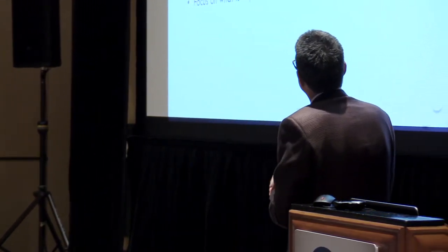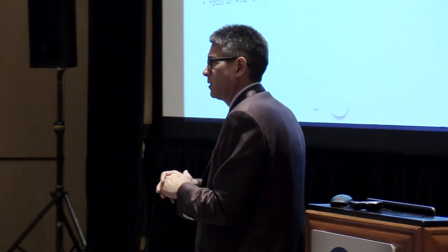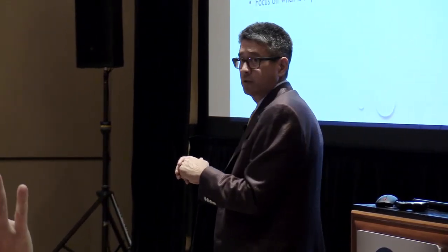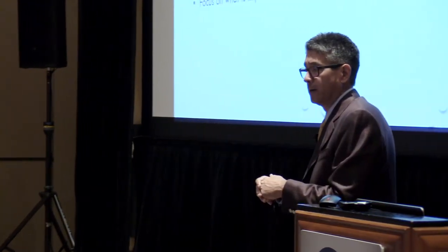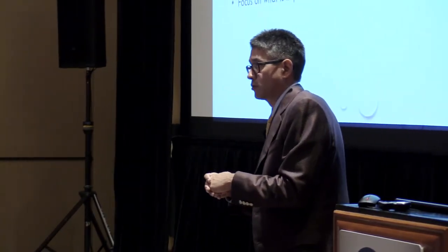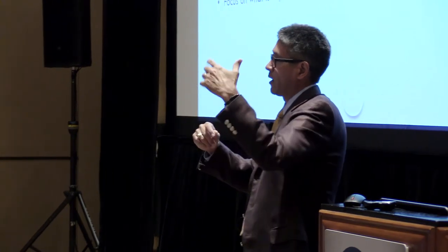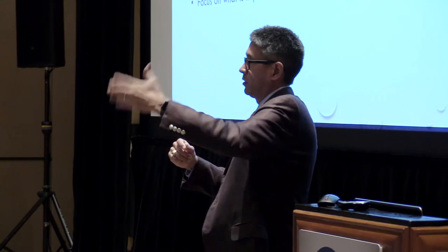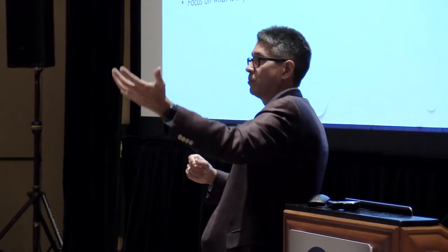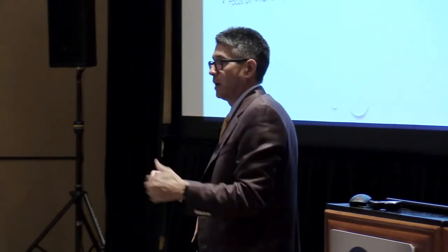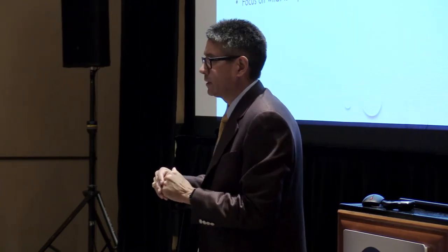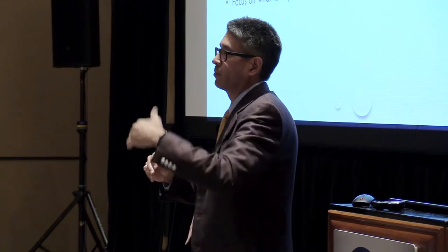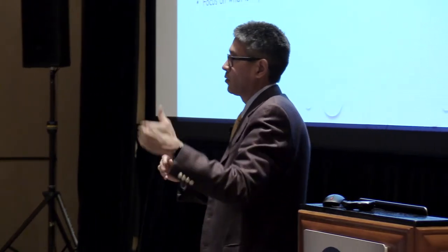Keep an eye out for new technology. Has anybody seen the differential pressure controllers that people are starting to use now? They're using those on branch piping. A lot of times they'll take that differential pressure controller and control a valve to a differential pressure for that wing or for that major branch or for that floor, which is a challenge to set up a little bit. As long as they can get their pressure, they seem to be working pretty well.